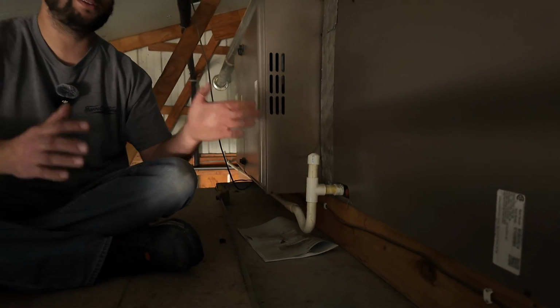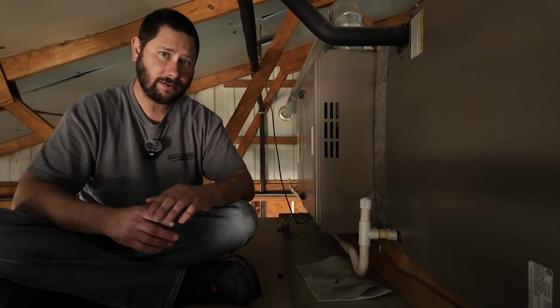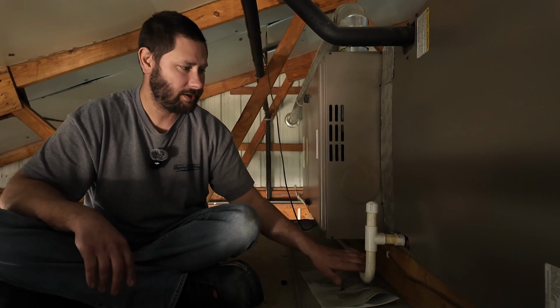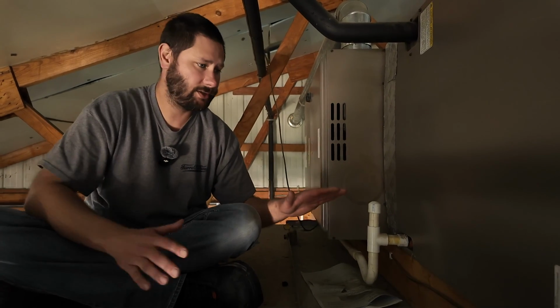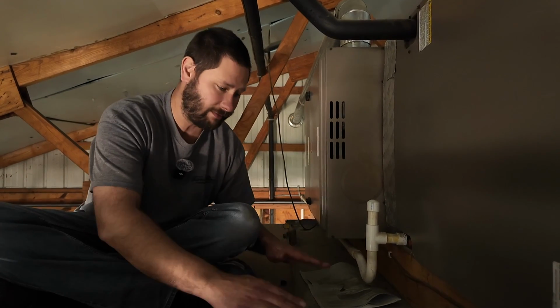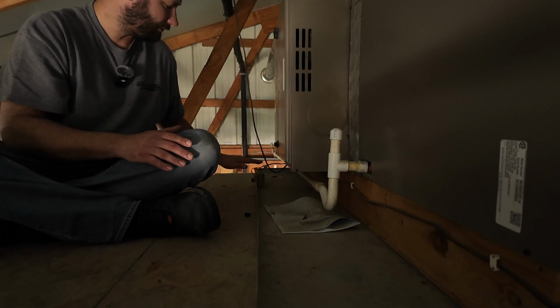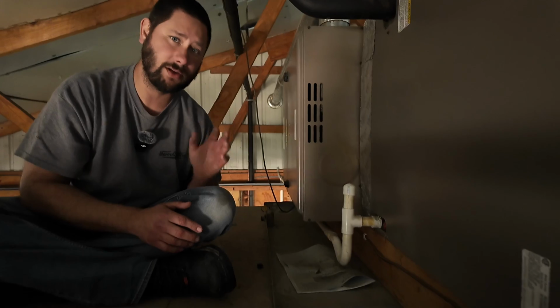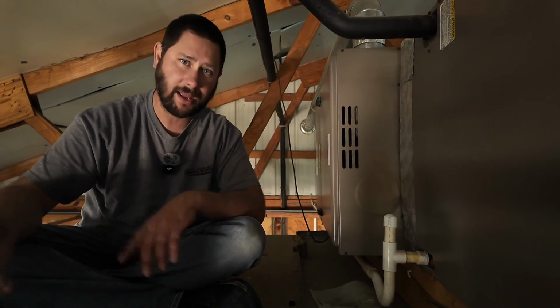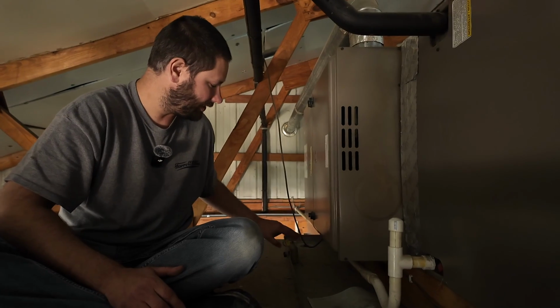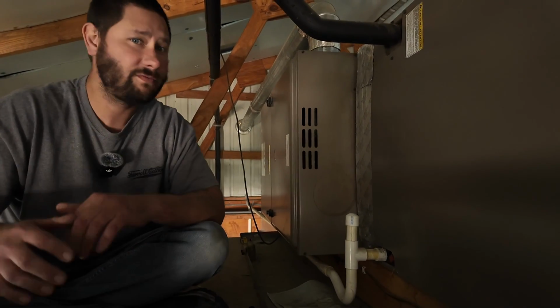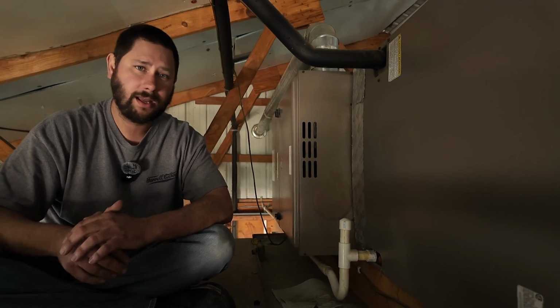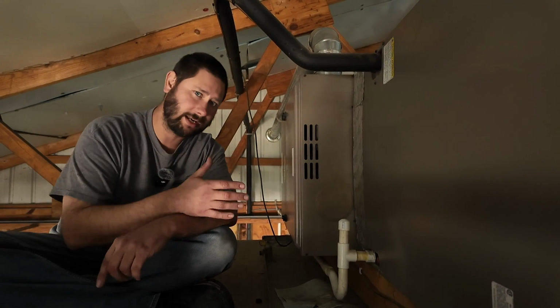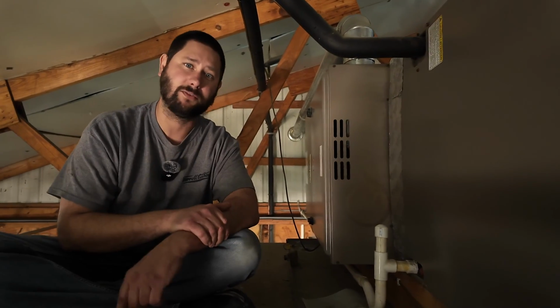If you do not clean out the drain and the unit's located in the attic, and then you leave and that drain gets stopped up, you're going to be responsible and it's going to cause some damage. You want to make sure that if you don't clean the drain, you have a pan that will catch the water with a float switch or a safety device that will cut the unit off before it spills out of the pan through the ceiling and ruins that customer's home. You don't want that, so make sure you just clean the drain. And you could also have a faulty safety switch like this float switch. I've seen them fail. And if they fail and there's a water issue and you were there to do maintenance, but you did not check everything and clean the drain, then you could have to pay for those repairs.